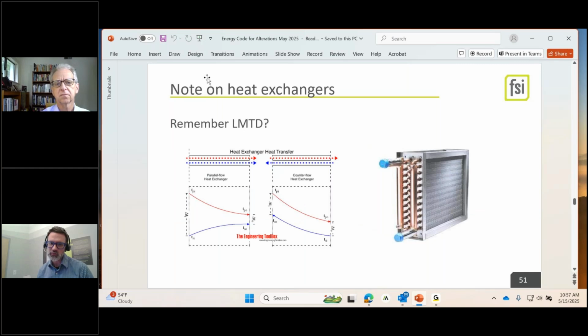Engineers in the room, this one's for you. Log mean temperature difference. You can't just be like, sure, I'm turning down from 180 to 160 and I'm sure it'll work. You got to start evaluating individual coils and what they work at with that. You got to work with your rep. You can't just assume the delta T moved down and I still get the same capacity. It doesn't work that way because you got your airstream temperature and your coil temperature to deal with, and the closer they get, the less heat you get, and it's logarithmic. So mind yourself. That's a painful lesson from me I can share with the world.